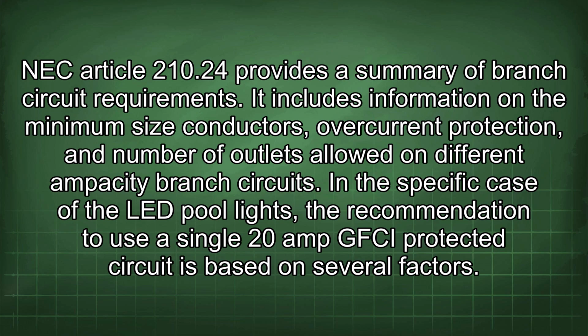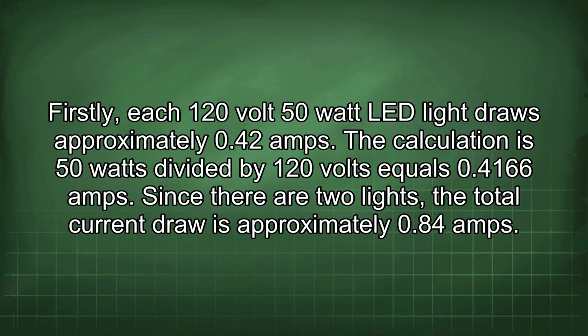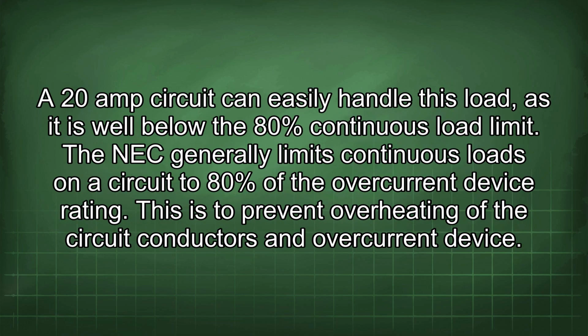In the specific case of the LED pool lights, the recommendation to use a single 20 amp GFCI protected circuit is based on several factors. Firstly, each 120-volt 50-watt LED light draws approximately 0.42 amps. The calculation is 50 watts divided by 120 volts equals 0.4166 amps. Since there are two lights, the total current draw is approximately 0.84 amps. A 20 amp circuit can easily handle this load, as it is well below the 80% continuous load limit.